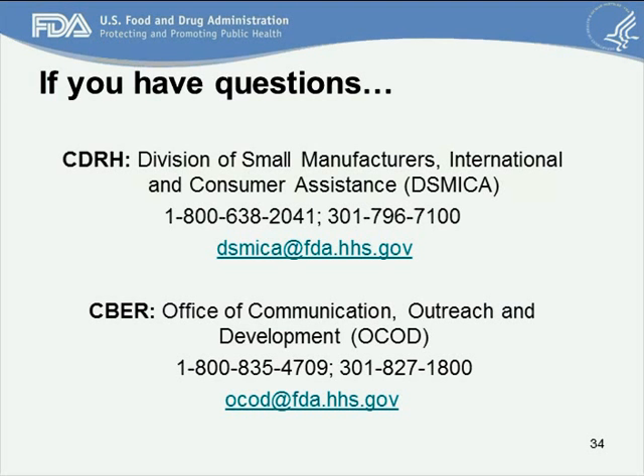It's not guaranteed, no, because we don't know what the data are going to be. If we're talking about the protocol in a pre-sub, we can give you feedback that we think this is going to be a good study to do and that it might likely support a 510K, but without knowing the outcome of the actual testing, we can't tell you for sure that it's going to support the 510K.